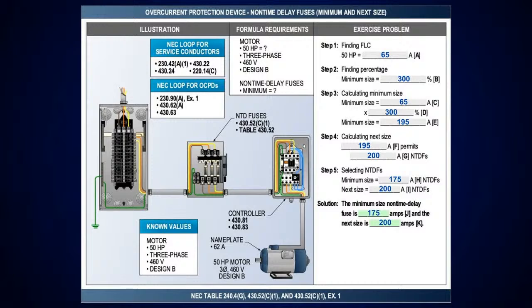All right? So I'm going to take the 65 amps at 300%. That's going to give me 195 amps. And then if I look at step 4, and I actually go over and look at 430.52(C)(1) A and B, it's going to tell you I'm automatically permitted to go up to the next standard size if it didn't start on the inrush current, which would be a 200 amp. But if it'll start based on not exceeding the calculated value, I can drop down to the next standard size, which is 175 amp. So we got a minimum size at 175 and a next size at 200.